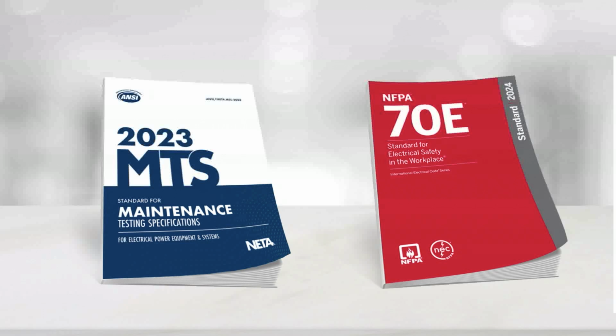I often talk about the NETA testing standards. When we go out and perform the NETA testing services, that's the maintenance and acceptance testing of electrical power equipment, part of that whole process revolves around electrical safety. So where do we go for electrical safety? We go to NFPA 70E. So there's a direct correlation between the NETA testing standards and the NFPA 70E standard for electrical safety in the workplace.